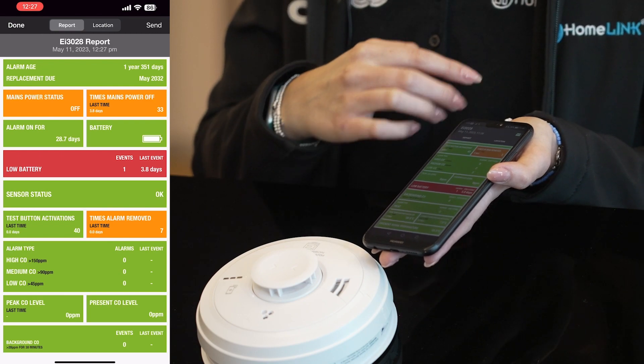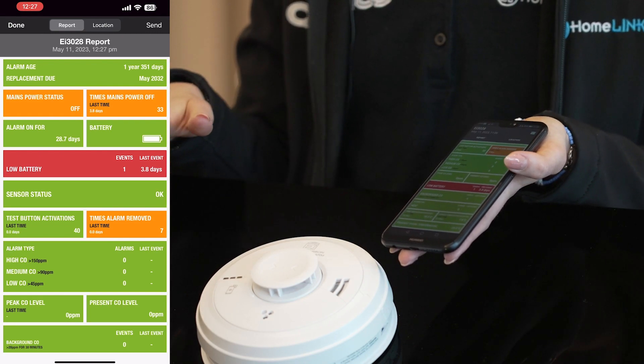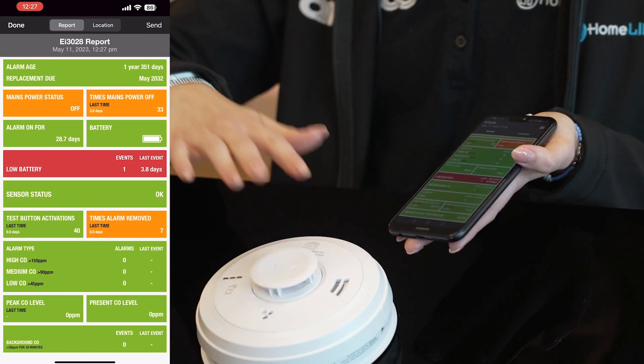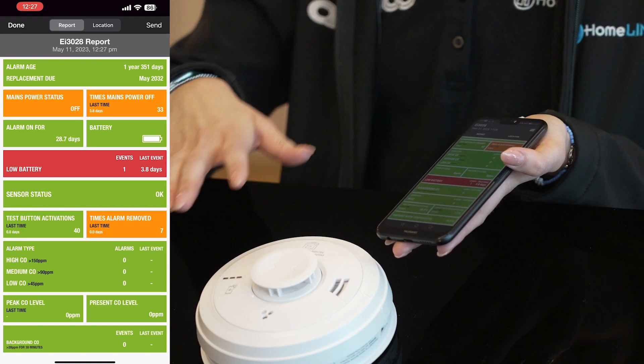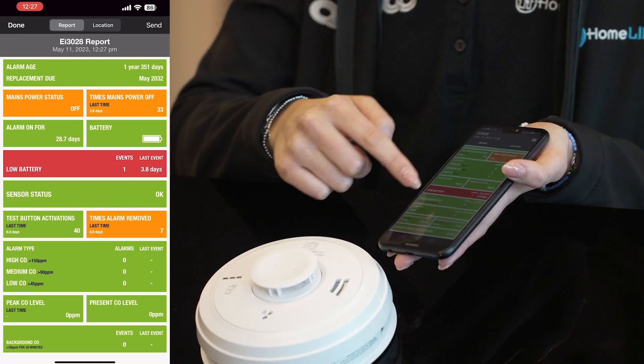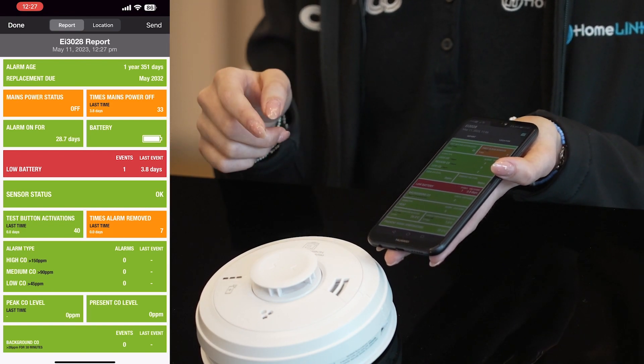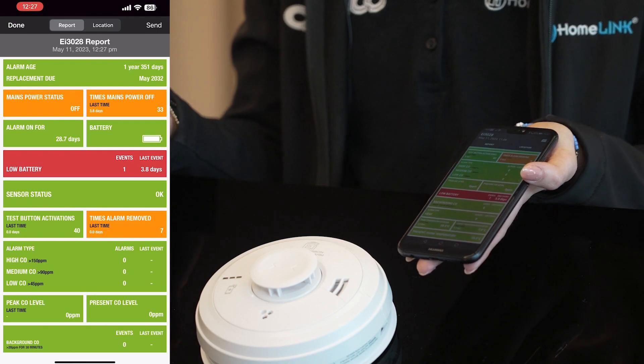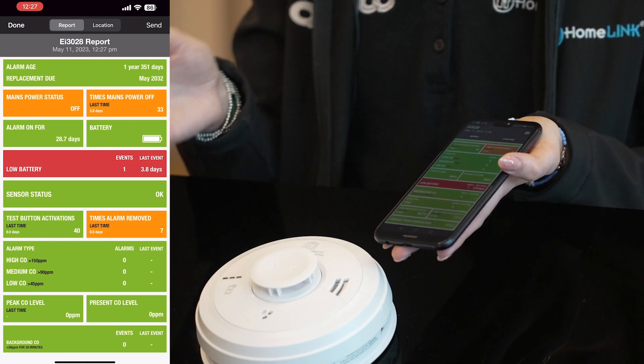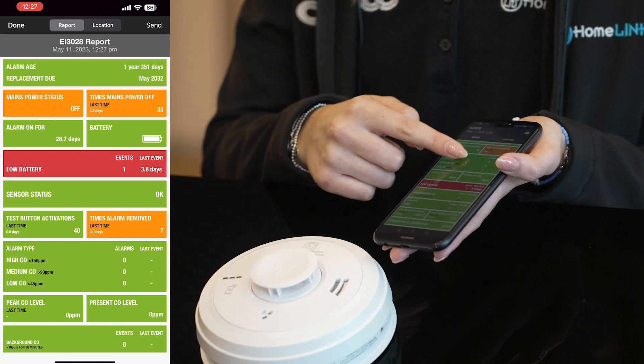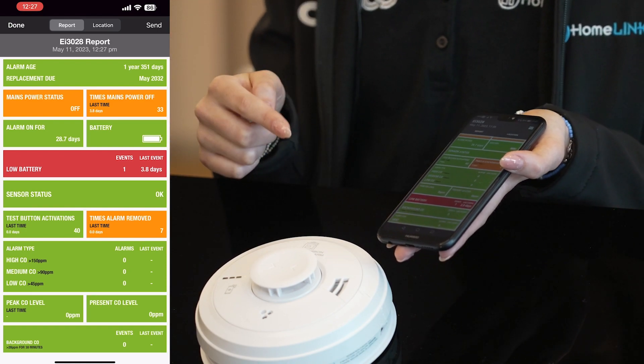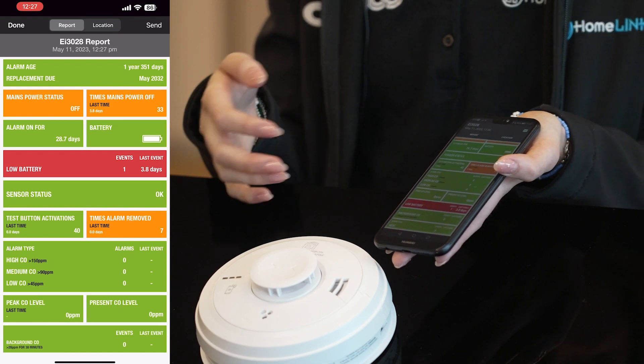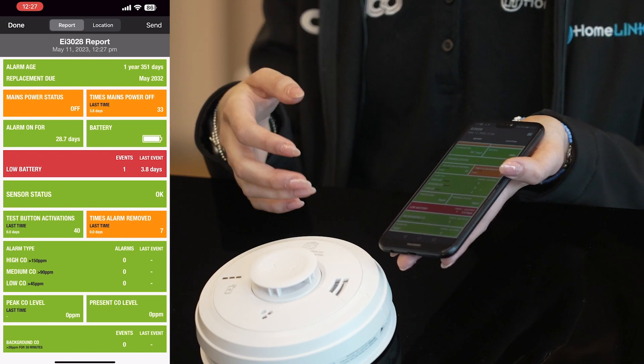You'll also be able to see any activation information, so if this alarm has been activated at all in its lifetime you'll be able to view it on here. That will be triggered by heat, smoke or CO depending on the alarm you've got. For CO activations, you will be able to see whether it's been a high, medium or low CO reading.